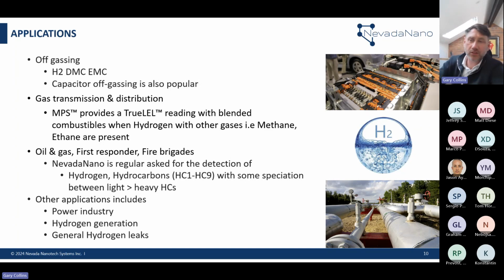Think about applications where fire brigades or first responders arrive on site with a portable device — they might calibrate to methane, and they really don't know what gases they'll encounter. The MPS provides a sensor that will react to all hydrocarbons, but also hydrogen, where a lot of the devices people have been using are IR based and won't detect it. We can also see heavy hydrocarbons that sometimes get filtered out on pellistors as well. So it's a real improvement on safety — if you turn up on site and might see hydrogen but also a wide range of combustibles, the MPS offers a more rounded and safer sensor, especially when you think about the true LEL element.